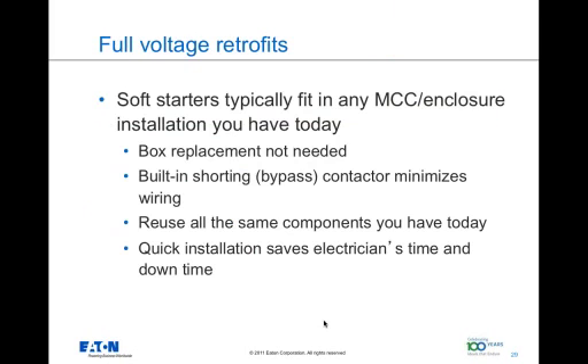Now at this point, if a customer is convinced that they need to use soft starters, then the question arises whether they can retrofit the existing starters with soft starters. The soft starters typically fit in any MCC or enclosure installation you have today. The enclosure doesn't need to be changed. You can use the same enclosure, and the built-in bypass contactor, which is integrated into the soft starter, minimizes any wiring and hence the labor associated with the electrician's time.